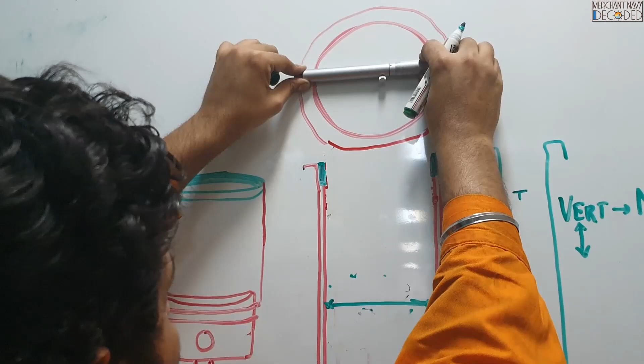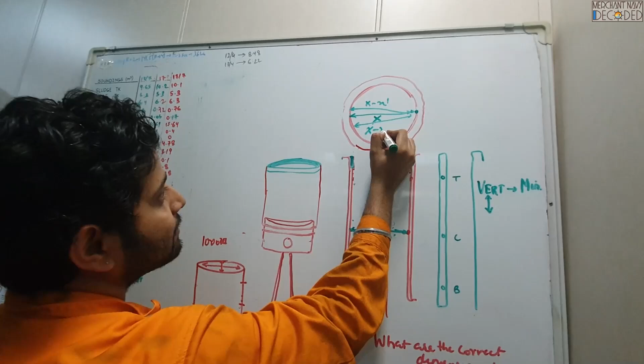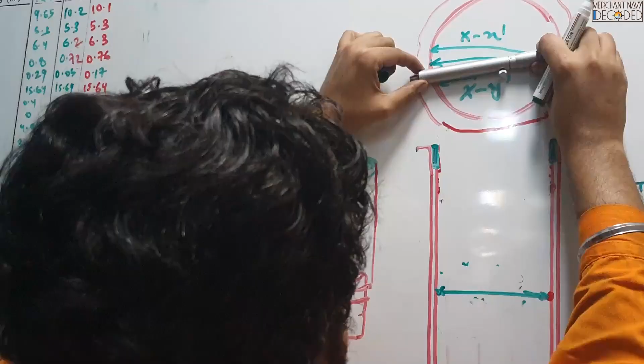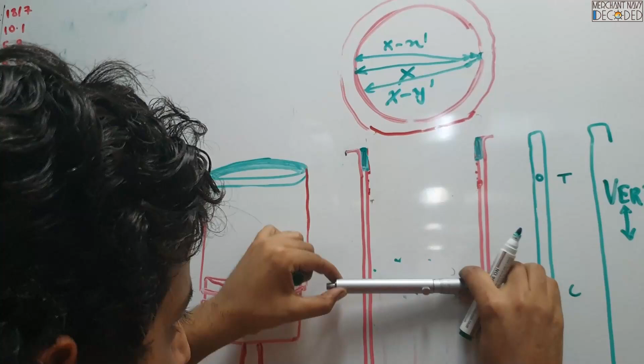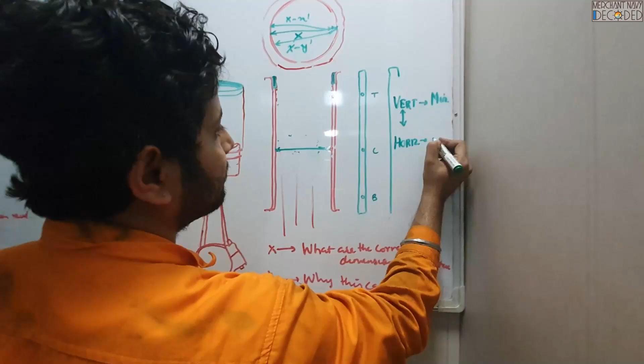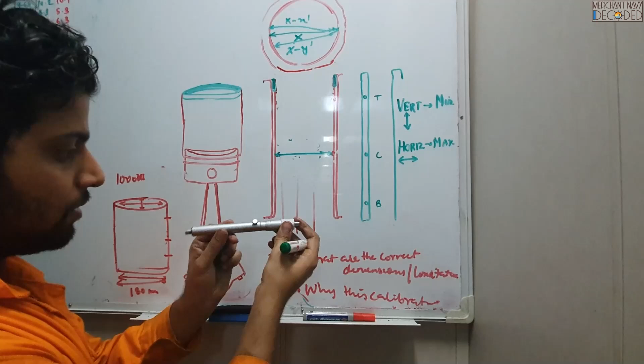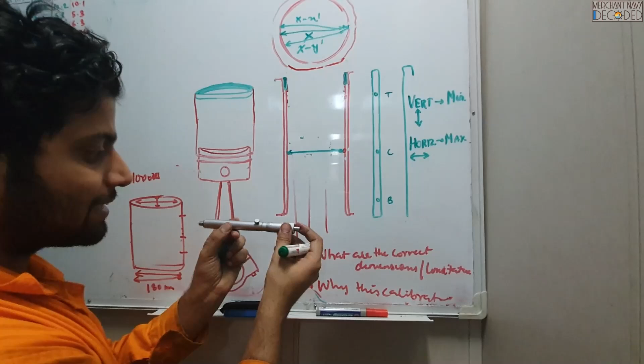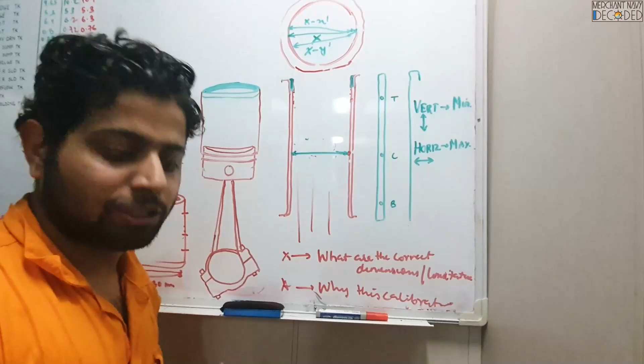So when I do the horizontal movement across this point like this, what I get is, suppose this is the point, and this is the point which is completely straight ahead. So this is say x, this distance will be x minus x dash, and this will be x minus y dash, right guys? So basically when we talk about horizontal movement like this, that is over here, then we need the maximum, that is the straight point. So when we do the horizontal movement, there we need the maximum value, that is, when these 2 points are combined together, when we move this way the maximum point we get this, then across this the minimum point, wherever it gets, that's the straight point, 180 degrees opposite. That is the exact liner calibration that we do.